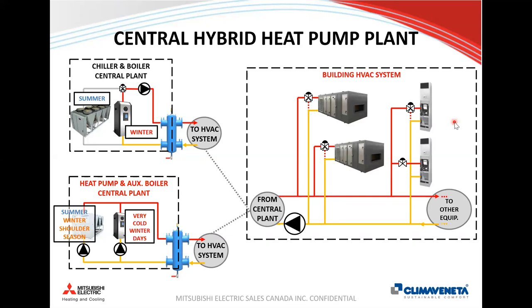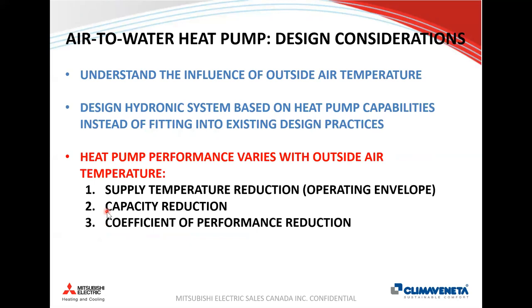The low-hanging fruit for contractors on this call is to add value by promoting air-to-water heat pumps instead of replacing air-cooled chillers like-for-like. Put it to work in winter instead of shutting the chiller down at end of cooling season. Most products on the market today — whether from Mitsubishi Electric or other manufacturers — have a best-case operating envelope cutout of around minus 20°C, with our product working to minus 15. In most of Canada, you'll still need an auxiliary boiler, which provides resiliency and redundancy.